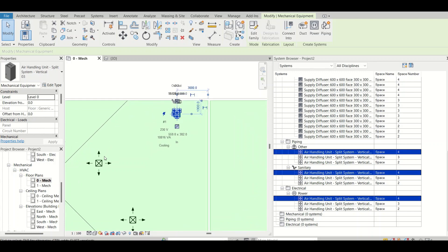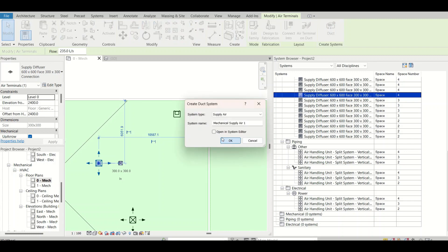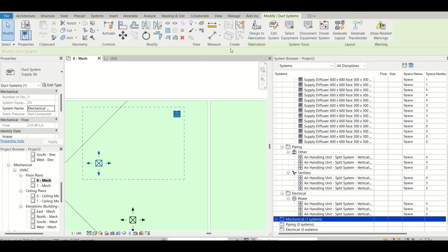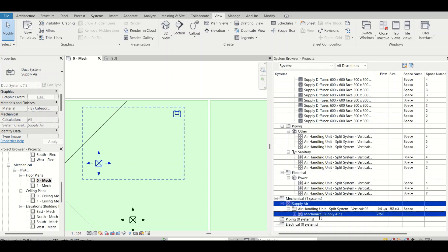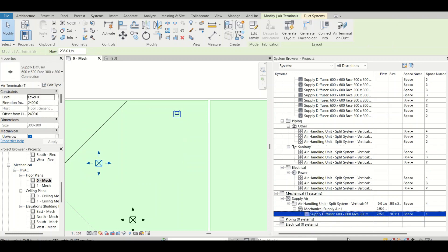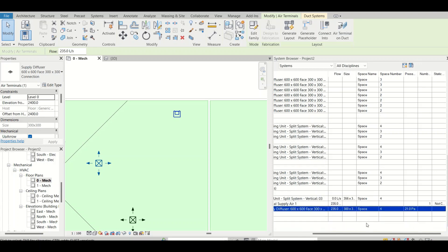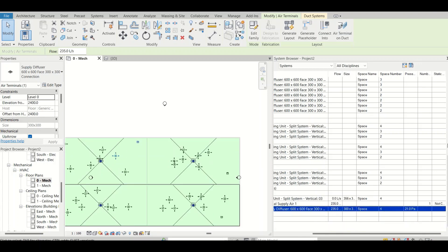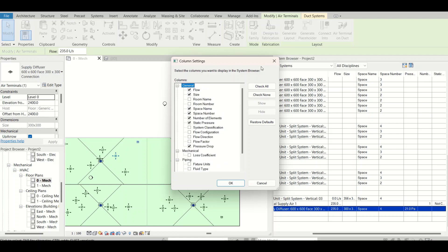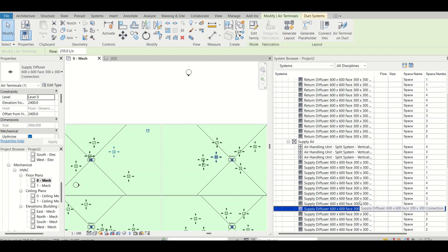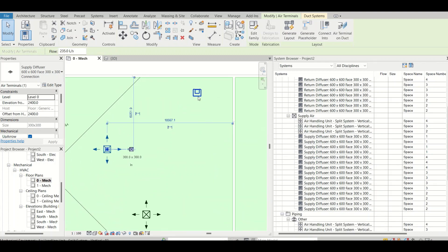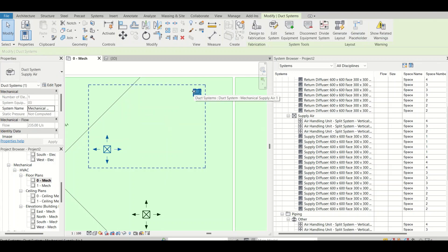If I select this air terminal and click on Supply Duct, then click Select Equipment and select the AHU, the system is now defined. Under Supply Air I can now see my AHU, my system, and inside the system I can see my diffuser as well. You can also see the space name — Space 4 — and parameters like pressure drop. You can add additional parameters here for piping, mechanical, or whatever you need to cross-check.